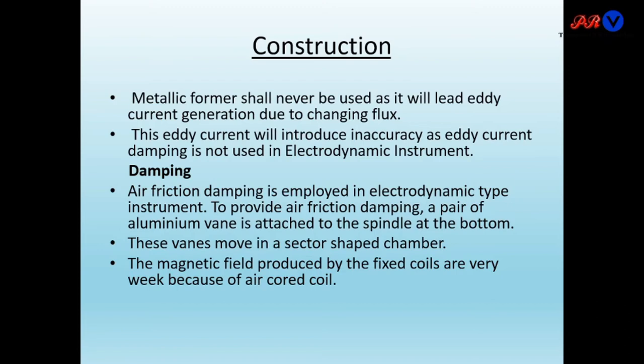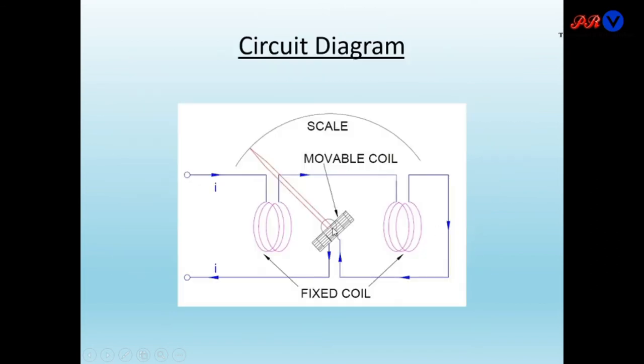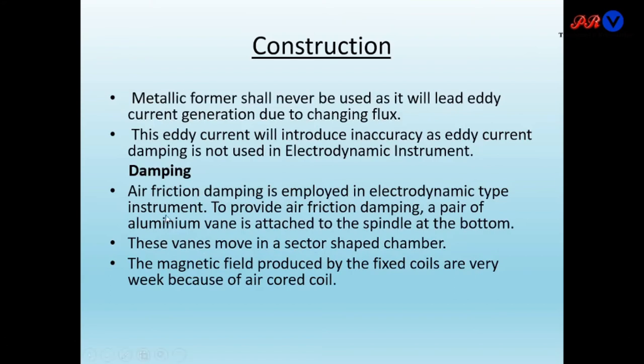A metallic former would introduce losses, and the eddy current would introduce inaccuracy since eddy current damping is not used in electrodynamic instruments. Air friction damping is employed instead. To provide air friction damping, a pair of aluminum vanes is attached to the spindle at the bottom, and these vanes move in a sector-shaped chamber.